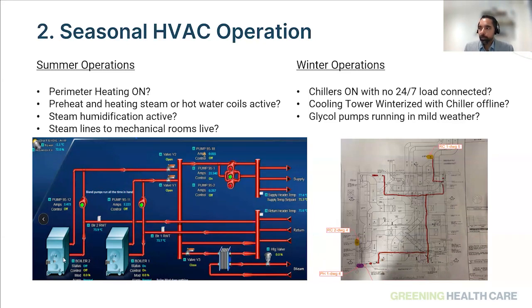Similarly, winterizing the cooling tower: if the chiller is offline, do you actually need it? Because in most cases you don't. And the glycol pumps running in milder weather: they should be programmed to run only when there's a call for heating.